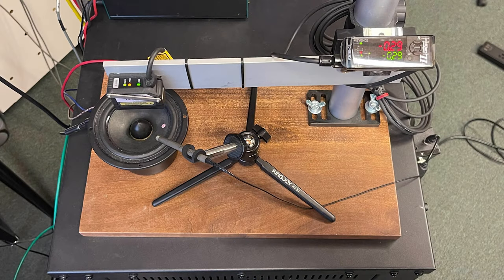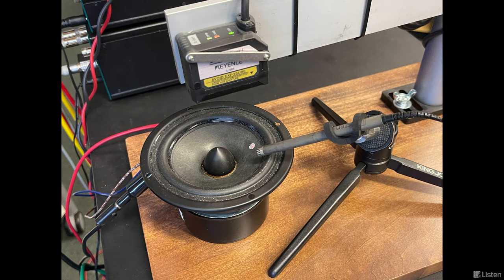Displacement lasers can be used to measure the peak displacement of a loudspeaker diaphragm at various power levels, frequencies, or both. Did you know that SoundCheck can easily be configured to include a laser signal path? This makes it easy to correlate diaphragm displacement with electrical impedance and audio artifacts. Let's take a look.